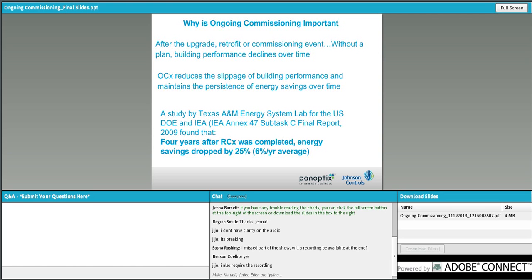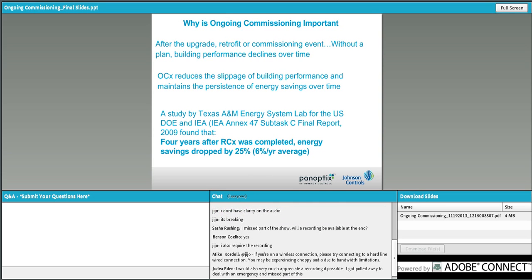So why is ongoing commissioning important? Every new building, after it's constructed, turns immediately into an existing building, which adds to the currently massive inventory of existing buildings. And existing buildings have a common problem, as Jim alluded to in his presentation. They suffer from loss of performance, ranging from high energy consumption to poor indoor environmental quality, poor IAQ, and poor occupant comfort. And even when a building is set up and running efficiently when it's originally constructed or remodeled, without some type of plan in place to maintain a high level of performance, that system performance will degrade over time.